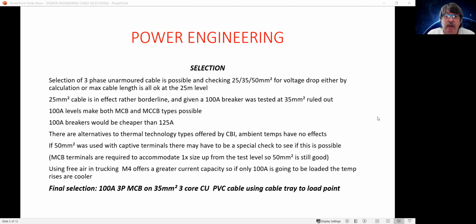So here's another direction from the circuit breaker manufacturers. You saw during the test that the specified cable would be 35 square. And in fact, the specification calls for the next size cable to be a possibility in the clamp system. So the 100 amp breaker is in fact equipped to go to a 50 mil square cable. By design, it's a forced design, obviously, a specification requirement. So that's a possibility as well.